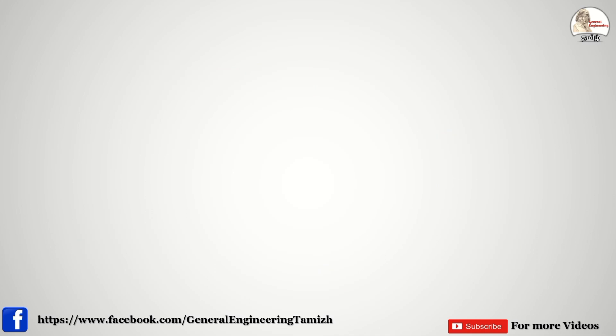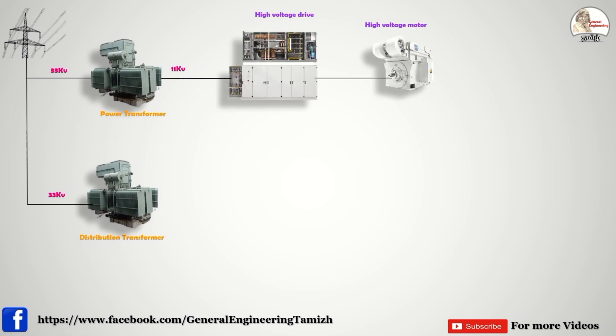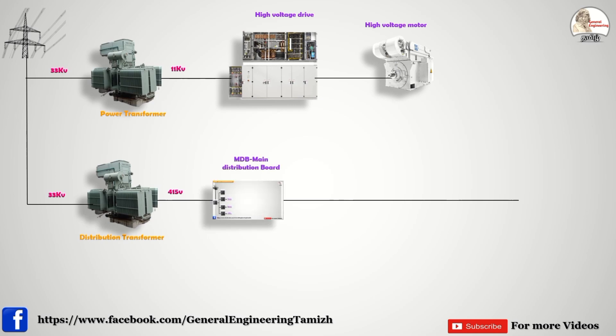Our plant incoming supply voltage is divided into high voltage and low voltage. High voltage — for example 33 kV — is converted to 11 kV through a power transformer. From 11 kV we connect high tension motors, drives, and other high tension equipment. Next, a distribution transformer converts 33 kV incoming to 415 V output. This 415 V must be distributed across the plant since 95% of equipment uses 415 V. For this distribution we use different types of panels in sequence. The first panel connected to the converted 415 V is the Main Distribution Board — the MDB — where all high kilowatt equipments are connected.